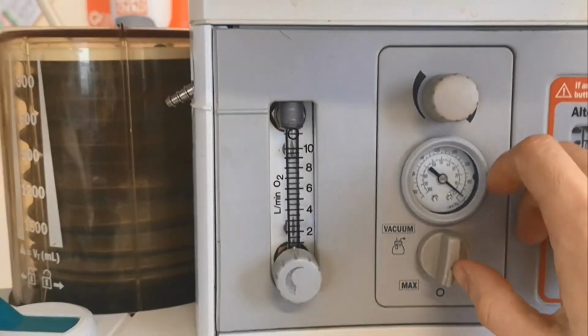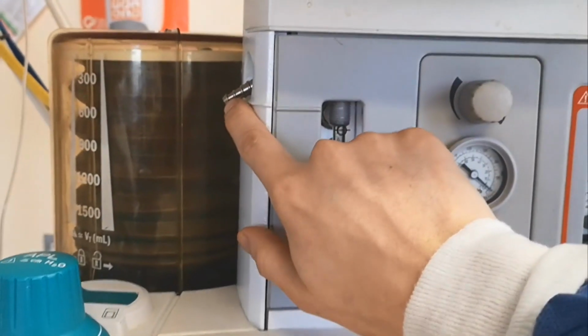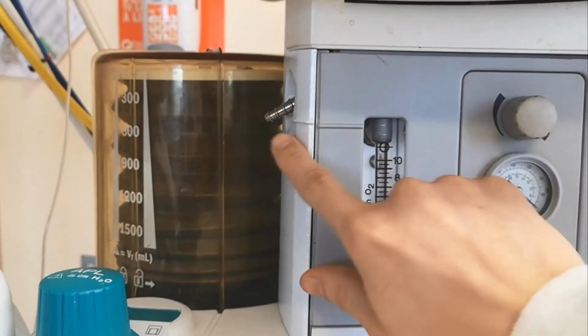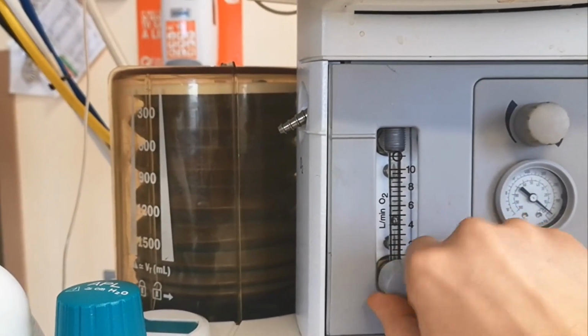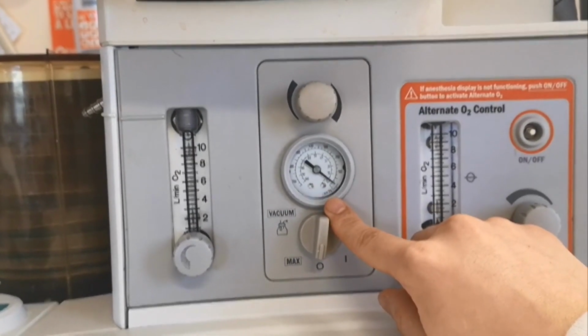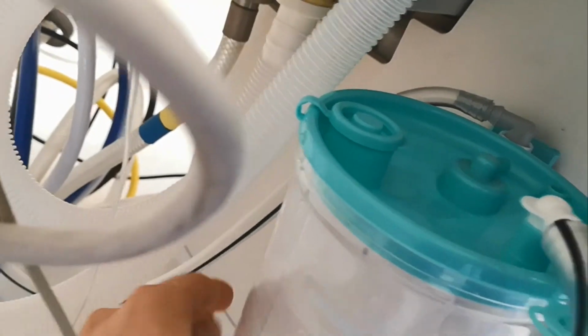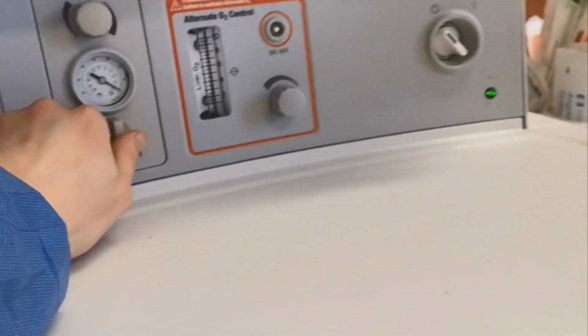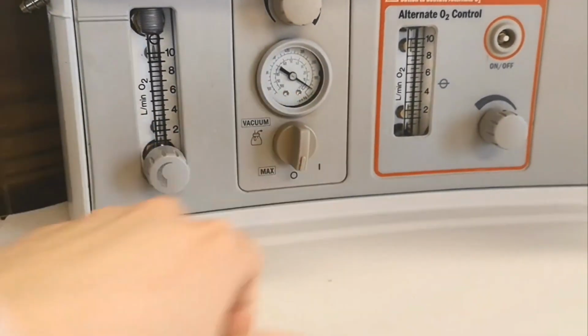Here you have an external oxygen supply that is not connected to the circuit. So basically, if you want to attach a face mask or a nasal prong, from here just go with the green line there and just open and close oxygen. This is a vacuum. Remember the yellow line? So here you have this chamber. It's the vacuum chamber that comes from the back of the ventilator in here, and up here that's the suction line that we use. Okay, that's a suctioning catheter, and then we switch it on and off from here.